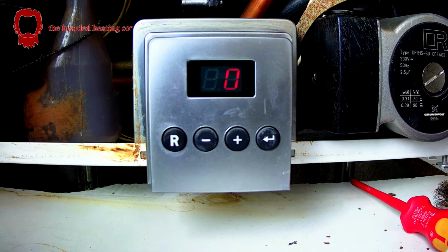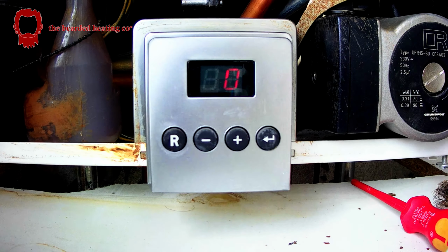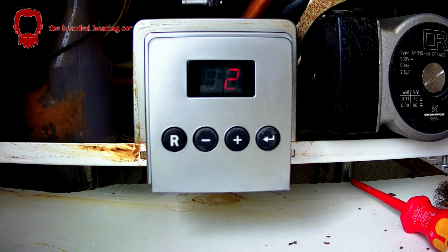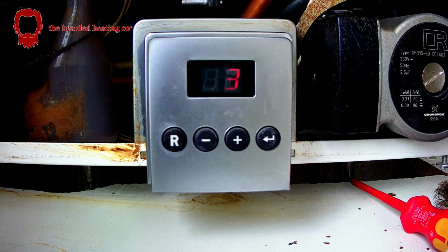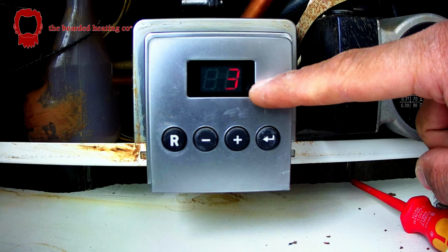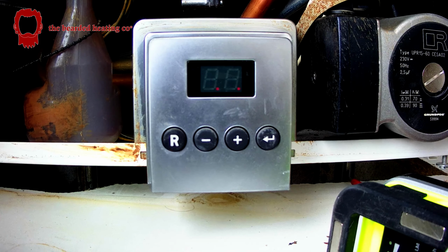So there you go, boiler's now on 0. I want to go and turn the heating on. And there you go, ignition sequence, code 3, status 3 means heating mode. That's it, heating is working. So now all I'm going to do is go and drain the water in a minute, recharge the expansion vessel, or check the expansion vessel charge, and change the PRV.